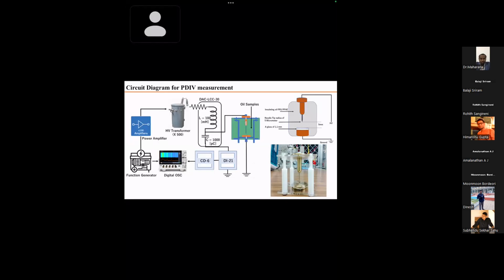Okay sir, one more question. We all know by thumb rule that for every 10 degree rise in transformer oil temperature, the breakdown strength drops by almost 50%. You would agree this is a thumb rule for mineral oil. So does the same relation hold good for ester oil as well? That means you're telling me that if temperature increases, breakdown voltage decreases. Yes, but does it reduce as drastically as mineral oil does?